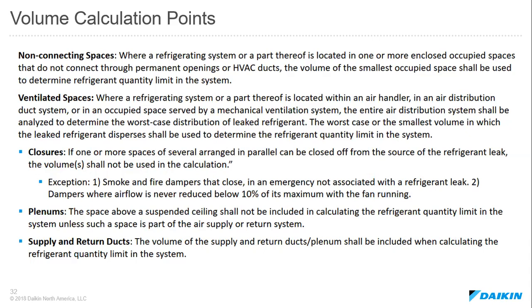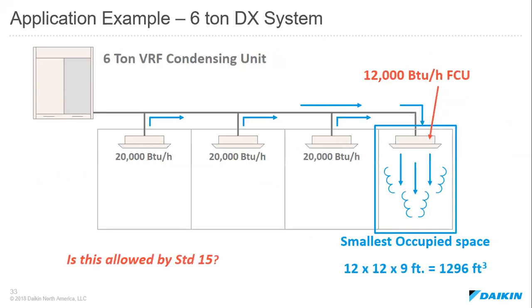There's closures, where we might have 1 or more spaces arranged in parallel that can be closed off from a refrigerant leak source. There also is, within a space, a plenum, which is the space above a suspended ceiling. And this space, unless it's being utilized as the air conditioning return, actually cannot be calculated or included in our volume for the space when we're doing our calculation. Supply and return ducts will typically be located within the plenum and will not count when we're calculating our refrigerant quantities. So here's our first application example.